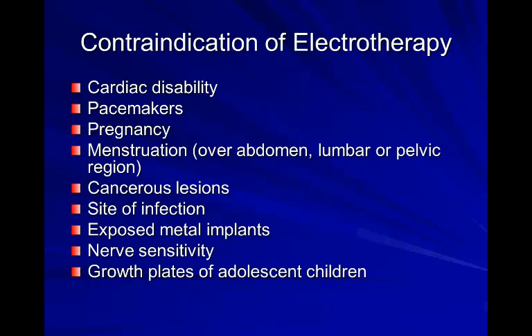Contraindications — reasons you wouldn't use electrical stimulation — include cardiac disability, pacemakers, pregnancy, menstruation especially over the abdomen or lumbar or pelvic region, any cancerous lesions, a site of infection, exposed metal implants, nerve sensitivity, and growth plates of adolescent children.